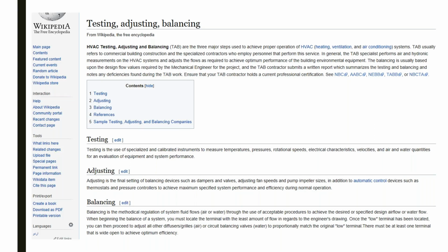Okay, so Chris, here's a question. We go and we're looking at a zone, and maybe it's been repurposed or whatever. They added some walls or took out walls. We'll say that happened, and we notice that our measurements don't match design. Well, I guess that makes sense. Someone adjusted these at some time. We don't know who. But we also know that people are complaining because they're too hot or too cold, or maybe both.